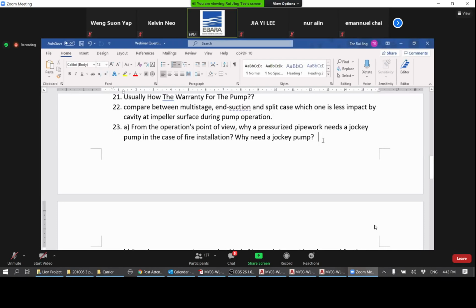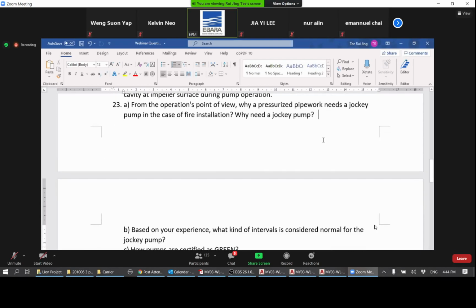Okay, number 23, from an operation point of view, why does a pressurized pipework need a jockey pump in the case of fire? Why do we need a jockey pump? Well, the idea is that in a fire system, your main duty as well as your standby pumps are usually bigger pumps. Depending on whether it's a sprinkler system or a wet riser system, the pump could be as big as 15 kilowatt, 20 kilowatt, 22 kilowatt, 30 kilowatt, and so on. So a jockey pump's function is just to ensure that the pipe is always pressurized, so that in case a fire happens and your sprinkler pops, the pressure is released immediately.